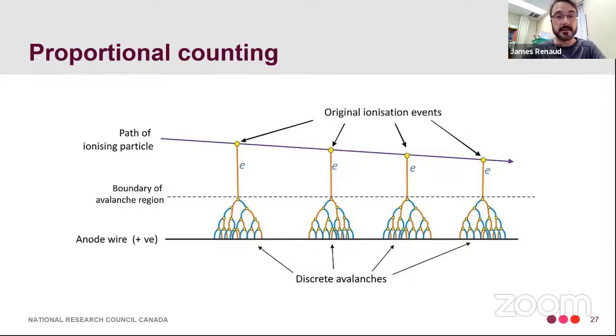So even though there's a large number of secondary ions for each primary event, the chamber is always operated such that the number of secondary ions is proportional to the number of primary events. This provides a form of amplification. This is the advantage of this method. In a typical proportional counter, you'd fill the container with an inert gas, which is ionized by incident radiation originating external to the chamber, as well as a quench gas to ensure that the discharge terminates. If you don't have a quenching gas, you can have events that produce spurious avalanches and pulses that keep going for a very long time. A common quenching gas mixture is 90% argon and 10% methane, and this is known as P10.